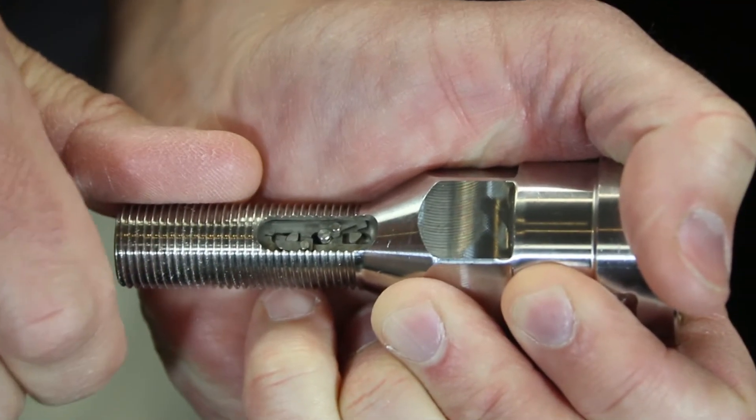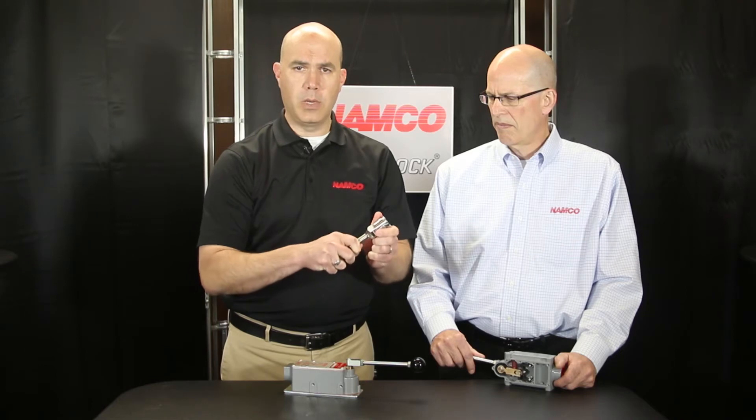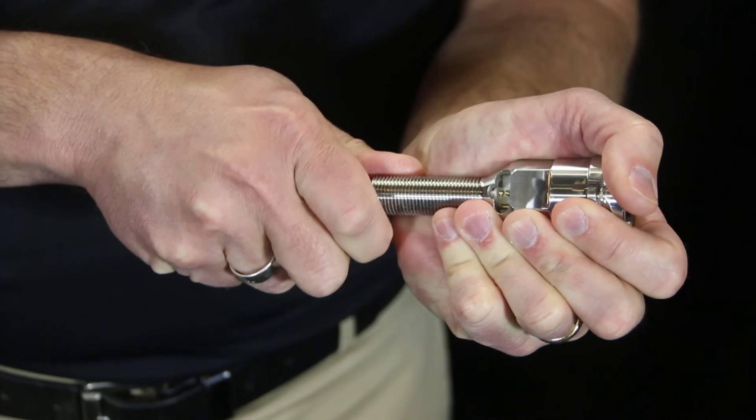We've achieved this smaller design by using the magnet as a target to actuate the switch. The contacts remain open even in a seismic event — it's not until I remove the magnet that the snap lock changes state.